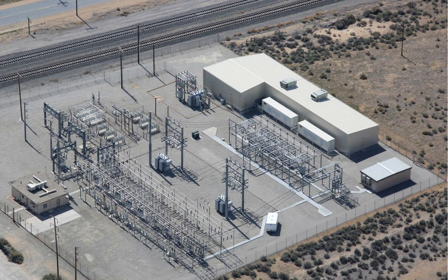This was the first known use of a subscale system by an entity other than a manufacturer or integrator to facilitate full-scale testing, commissioning, and ongoing operations. The mini-system test plan included two phases. 1. Performing safety testing on the expected behavior of the batteries and battery management system during interruptions to communication paths during system startup and operation, and 2. Performing system acceptance tests on the mini system to verify correct operation of the control algorithms, test modes, and system response prior to performing the same tests on the full system.